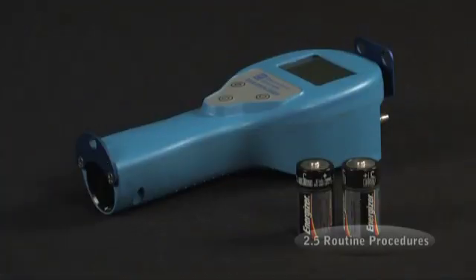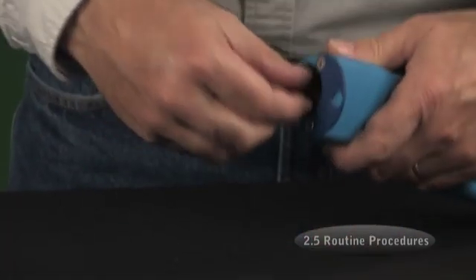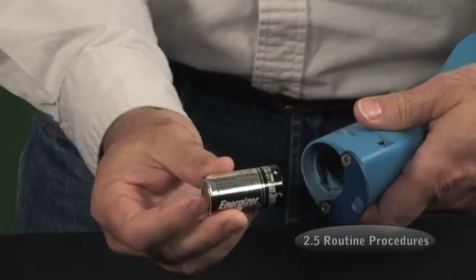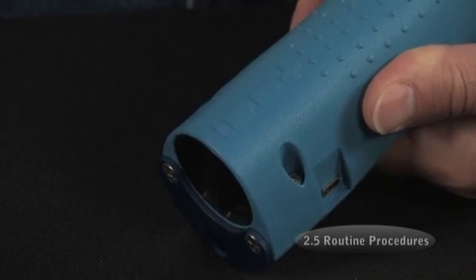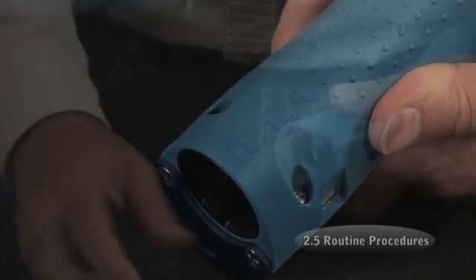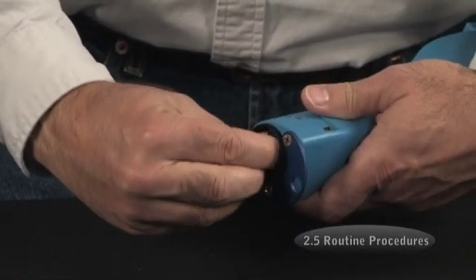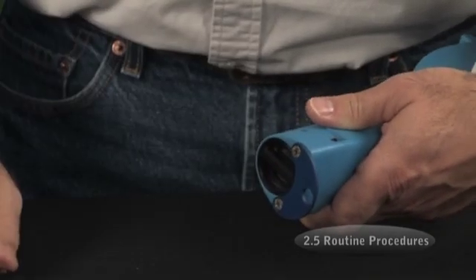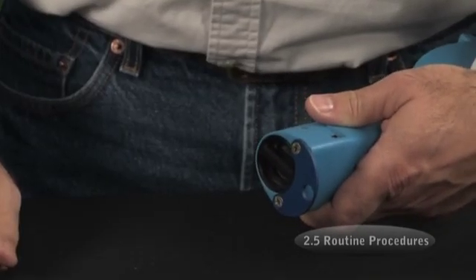As described previously, each gas Explorer comes with a set of alkaline batteries. To install the batteries in the Explorer, remove the cover at the bottom of the case and insert the battery's positive end first, as marked on the back of the Explorer. Replace the cover by inserting with the bar horizontal, pressing down, and turning 1/4 turn clockwise.